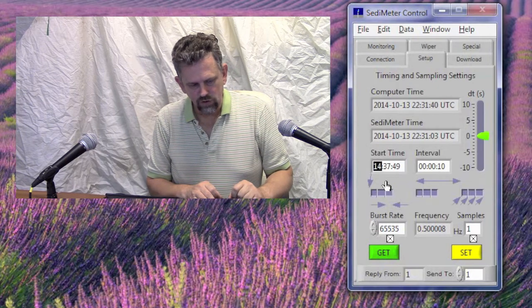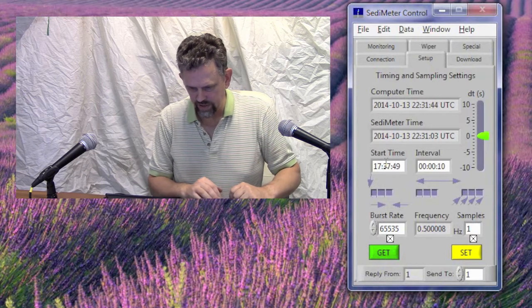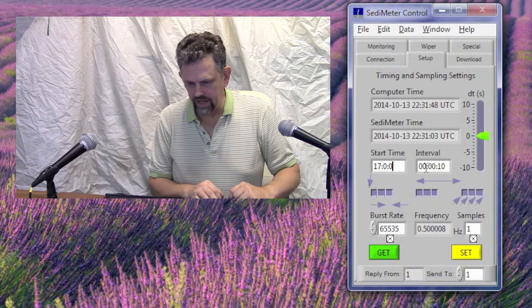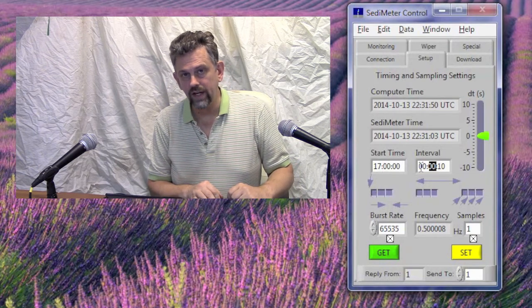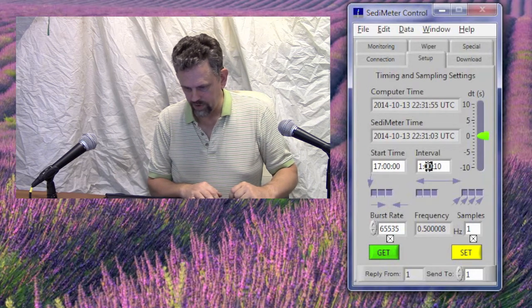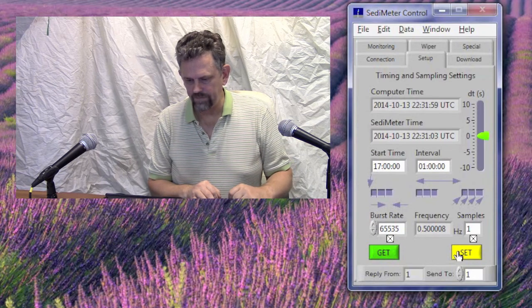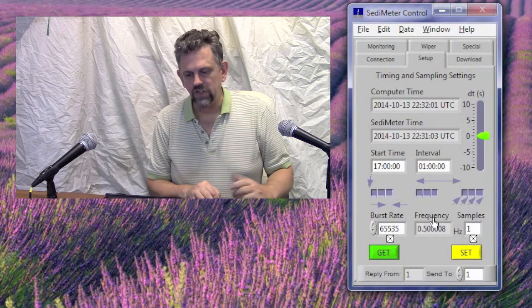Let's say tomorrow at 12 here is 1700 UTC. And the interval in hours, minutes, and seconds — perhaps we want to measure every hour, so we set 1:00:00 and click Set. The burst rate and the samples — those values you should ignore because those refer to other instruments, not this one.